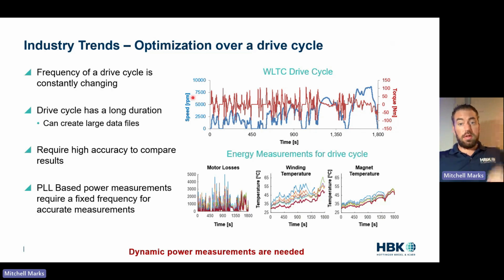So there's issues with this, kind of alluding to the previous part. Frequency of a drive cycle is constantly changing. There is no fixed frequency. So phase lock loop based systems are constantly looking for a frequency and they're not finding it. So if you're not using a cycle detect method, you're just constantly getting wrong answers. There's also the issue of going to quite high speeds, going to stop, and really having the accuracy across that frequency range. So understanding, am I accurate at the low speed, at the high speed? So there's that element as well. So it actually is a quite challenging measurement issue, especially if you're taking this drive cycle and looking at something like losses.